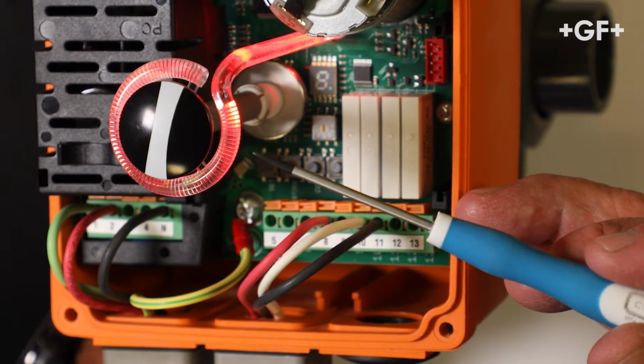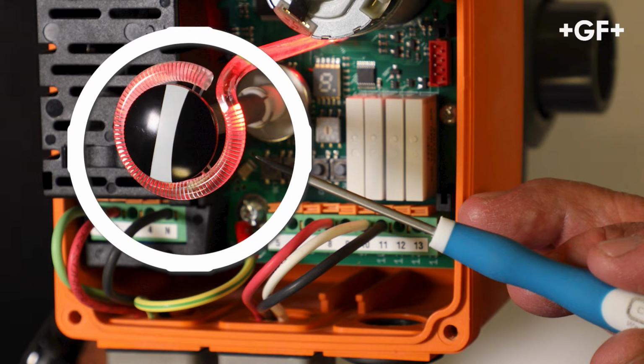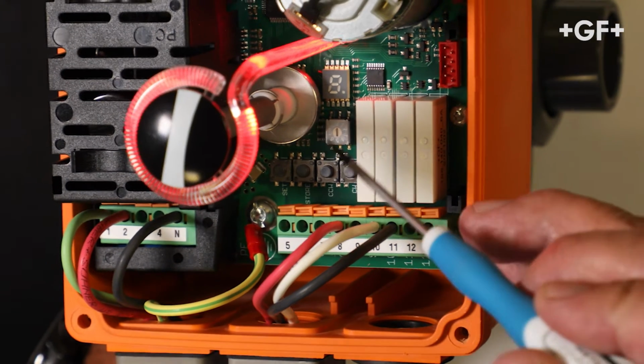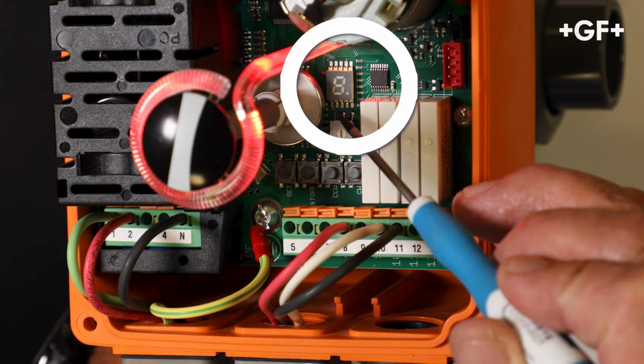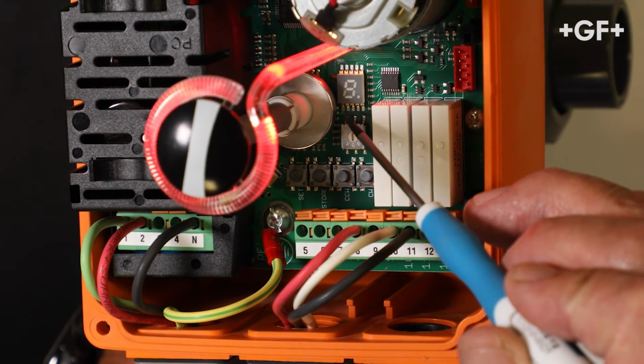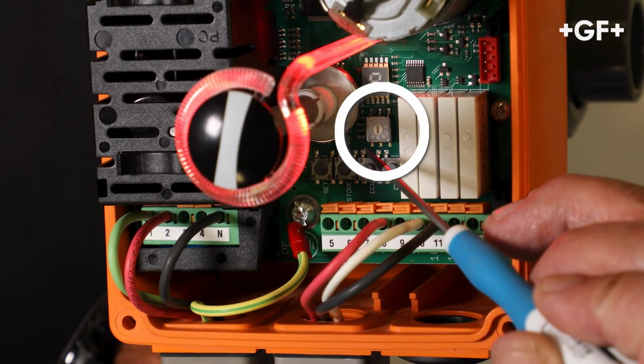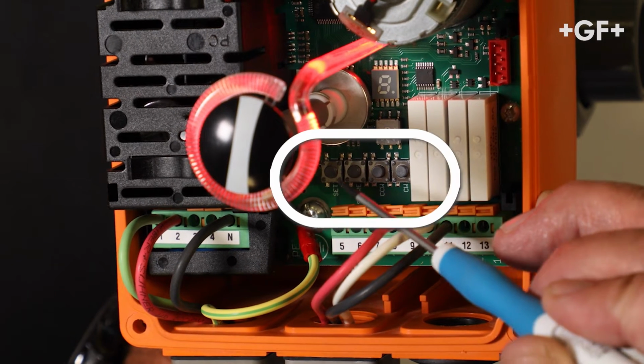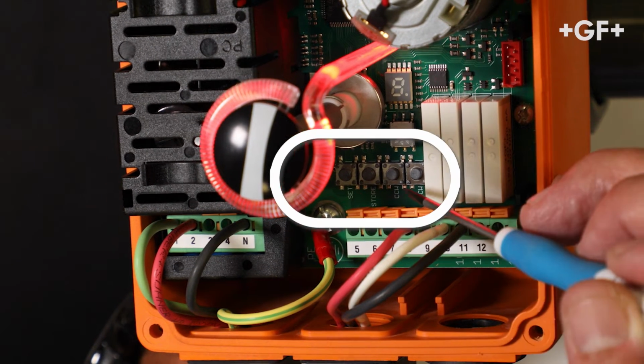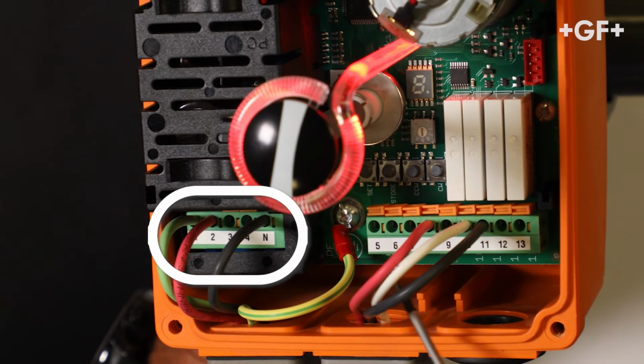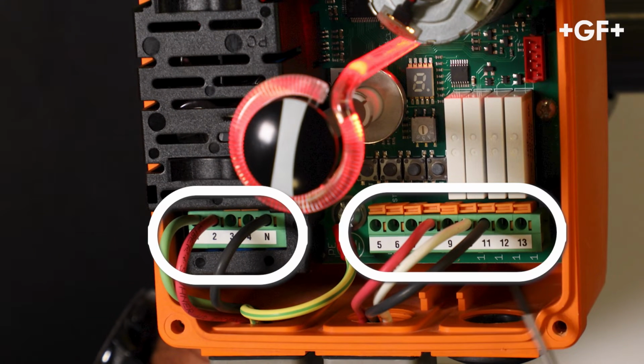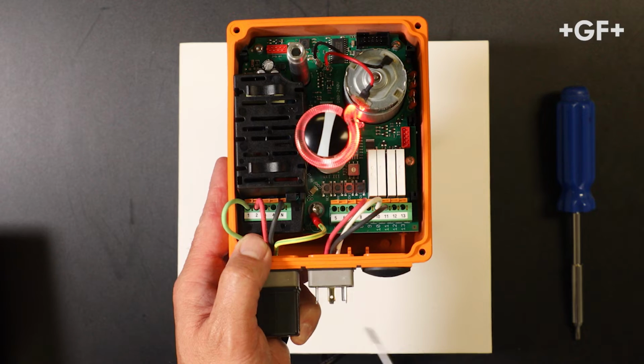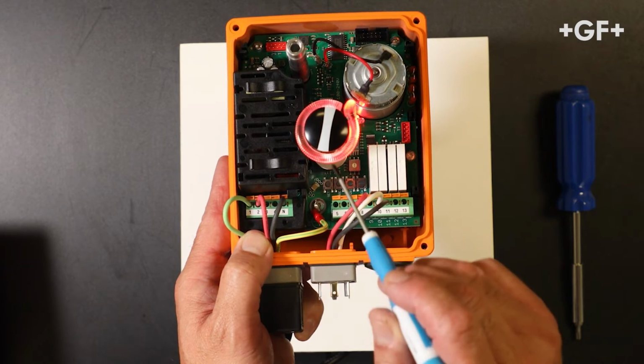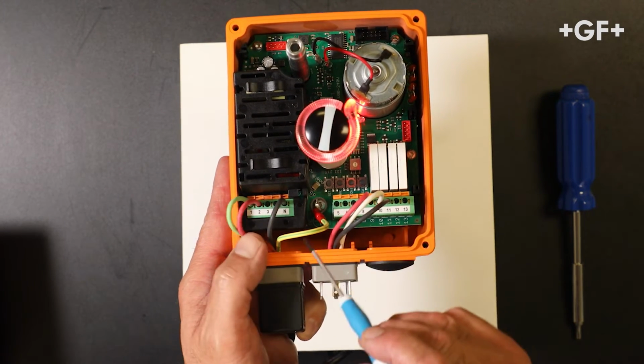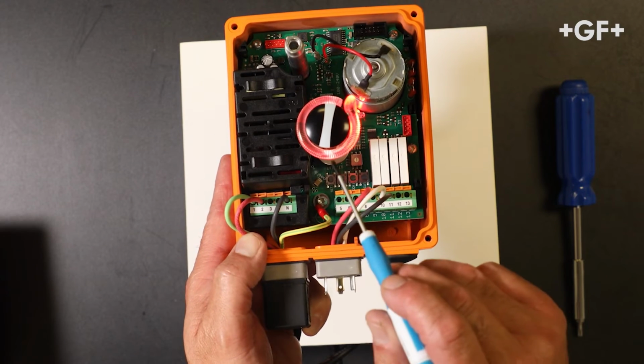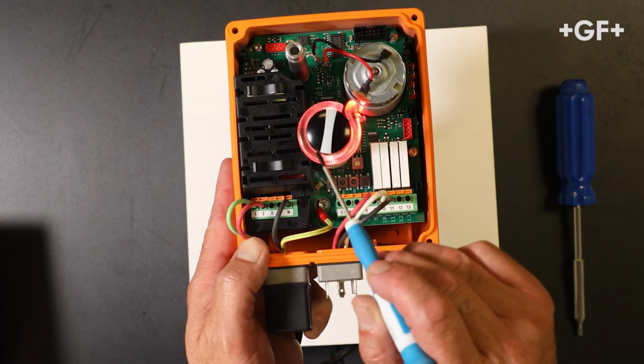Inside, you'll find the LED light tube for visual indication and valve status, 7-segment display for identifying error codes, and an integrated heater with adjustable settings, teach buttons for programming and adjustments, control, and feedback terminals. Note, voltage to terminal 1 will rotate the actuator counterclockwise. Voltage to terminal 2 will rotate the actuator clockwise.